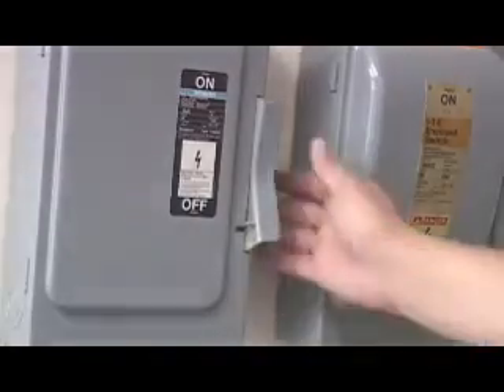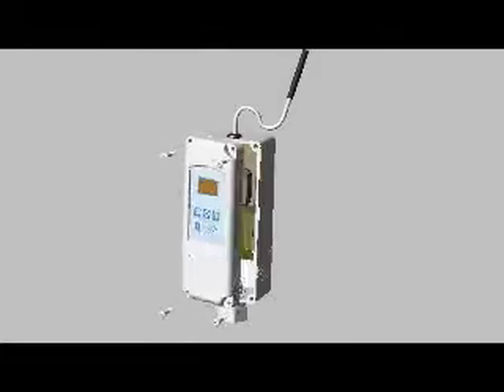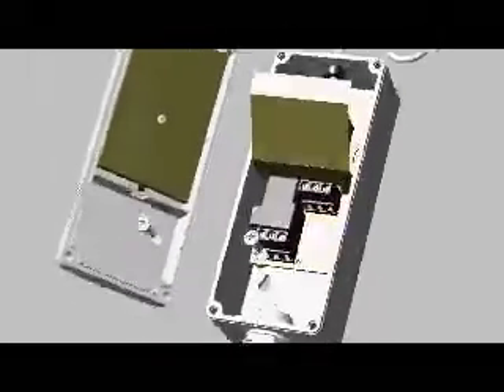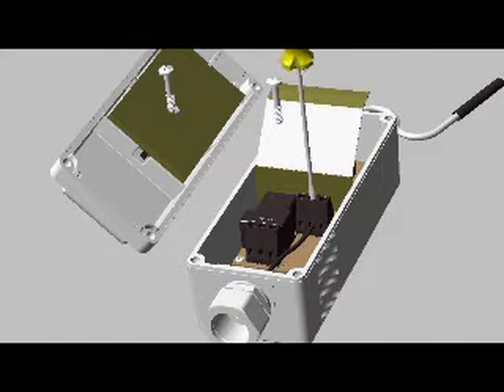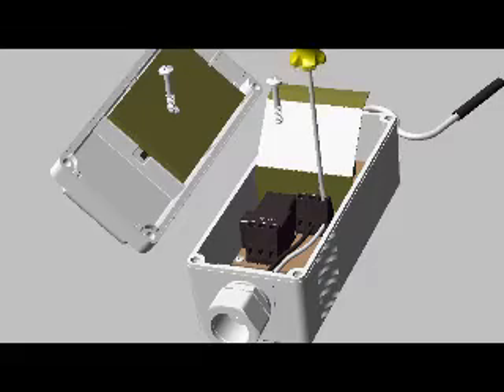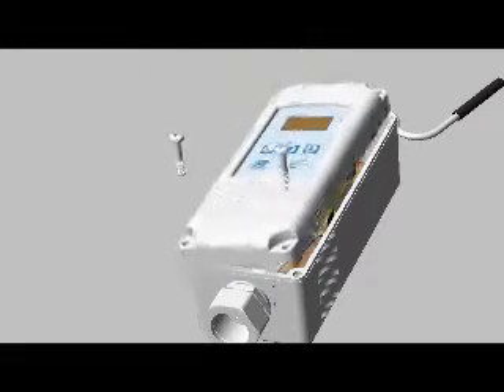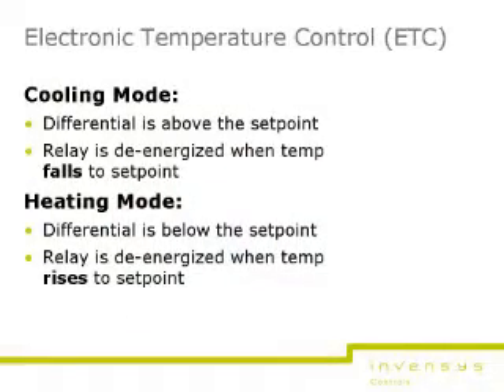Now that the unit is mounted, you are ready to do the electrical work. 1. Turn off all power to avoid personal or equipment damage. 2. The line voltage common should be connected to the COM contact and to the load. The line voltage line should be connected to the C contact and the appropriate input voltage contact. 3. The load should then be wired into either the normally open or normally closed contact, depending on application. 4. When the cooling mode is selected, the differential is above the set point. The relay will de-energize as the temperature falls to the set point. 5. When the heating mode is chosen, the differential is below the set point, and the relay will de-energize as the temperature rises to the set point.